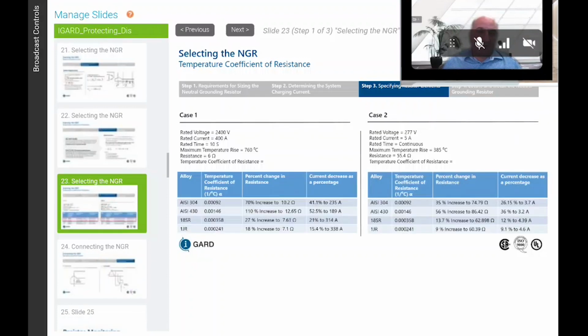I'll give you a better example of that. That's confusing, I'm sorry. So let's look at a low resistance ground in this system: 2400 volt, 400 amp, for a 10-second resistor. Your temperature is 760 degrees C above ambient, so we're using C57.32 here. So the resistance ends up being 6 ohms.